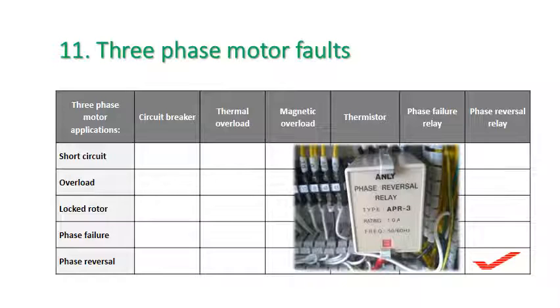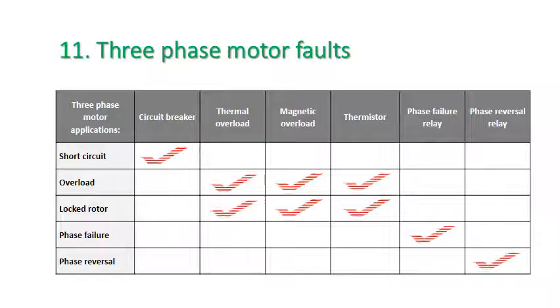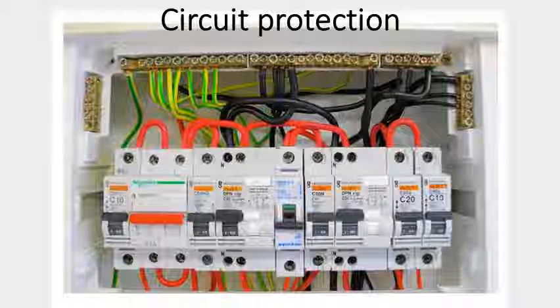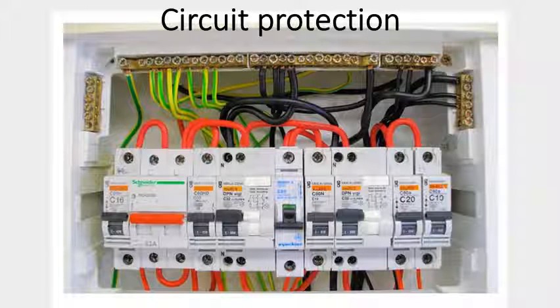If there's a reason that we don't want the motor to go backwards, if it's really important that the motor doesn't go backwards, if it's going to produce a dangerous situation, then we can use one of these relays to stop that from happening. So there you have it. There's our choices for protection devices for the different faults that we've got on this chart here. That brings us to the end of our series of videos on circuit protection.